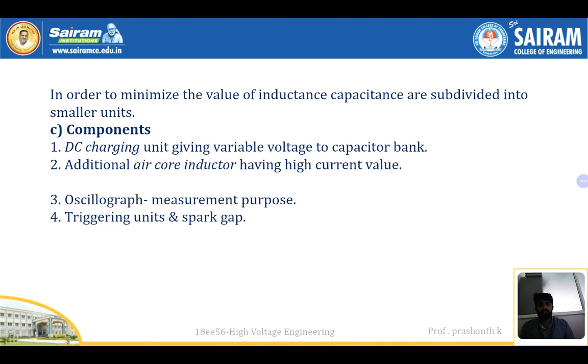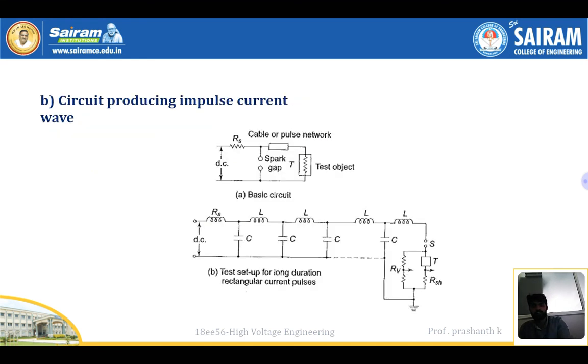In order to minimize the value of inductance, the capacitance is subdivided into smaller units. Components like the DC charging unit, additional air core inductor, oscillograph, and triggering unit spark gap will be there. Just see here, the components are present: spark gap, test object, and cable pulse network. This is the basic circuit. This is the test setup for long duration rectangular current pulses.